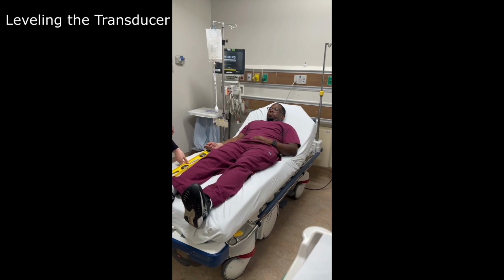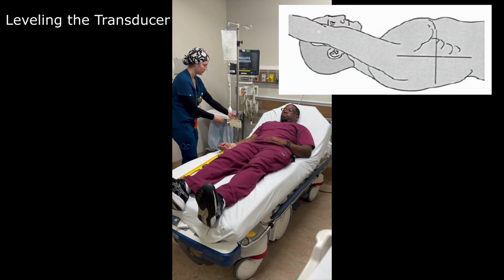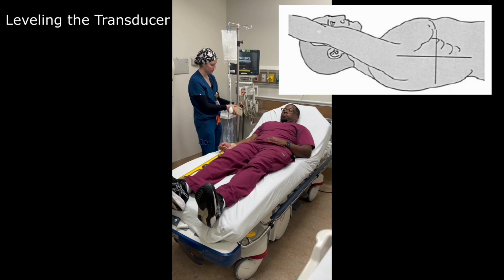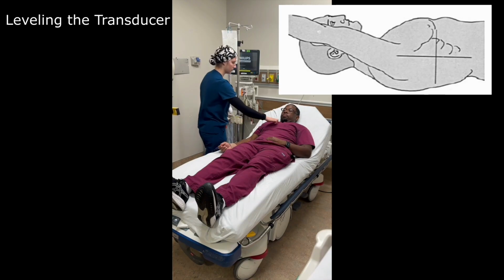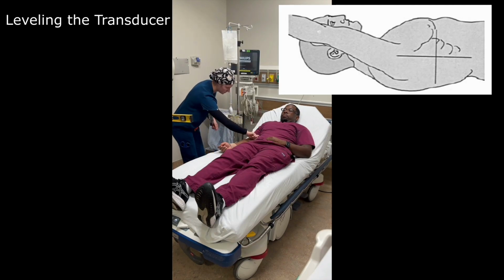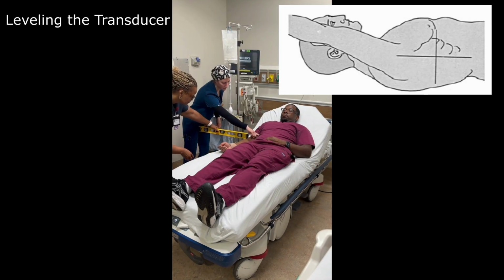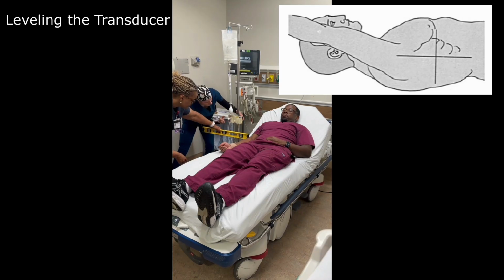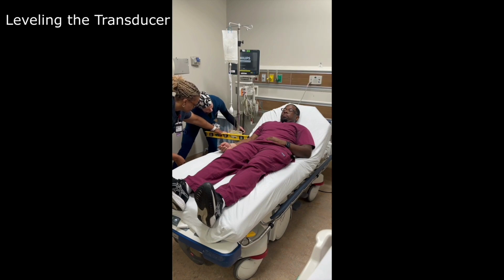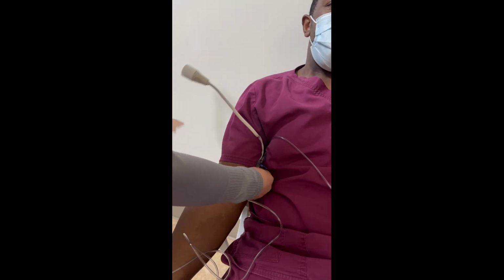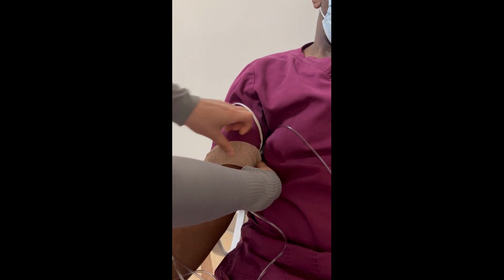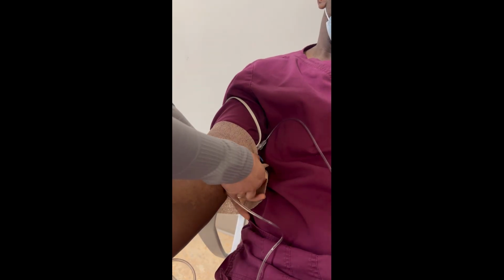Accurate pressure readings depend on proper leveling. Level the transducer at the phlebostatic axis, the fourth intercostal space at the mid-axillary line. This represents the level of the right atrium. Here I am palpating for the angle of Louis to find the second intercostal space, then walking it down 2 additional rib spaces and moving to the mid-axillary line. We place our leveling device to ensure a true horizontal, then raise or lower the transducer holder. Make sure to reassess with each change in patient position. Alternatively, you can coban the transducer directly to the patient's arm at this same level.